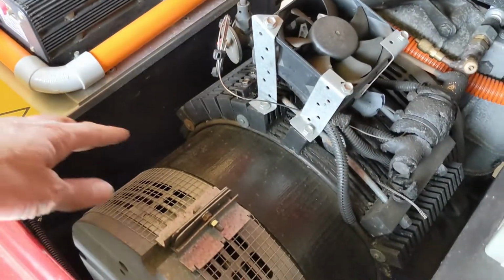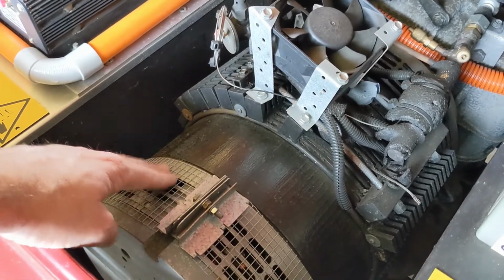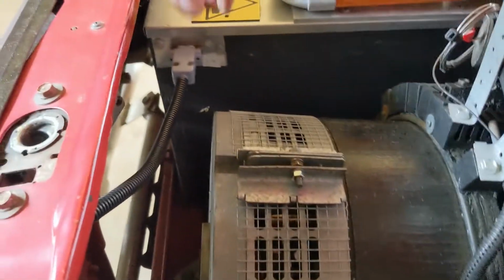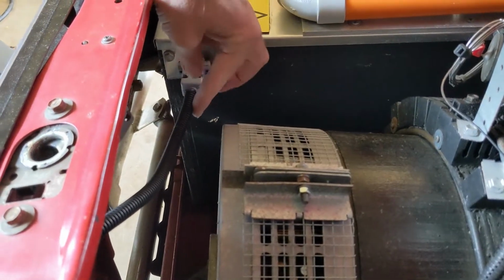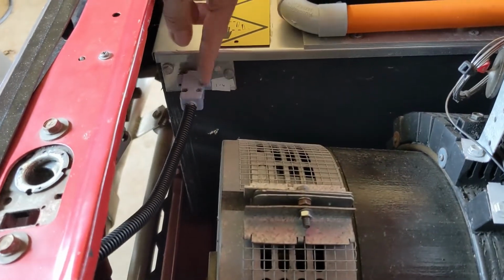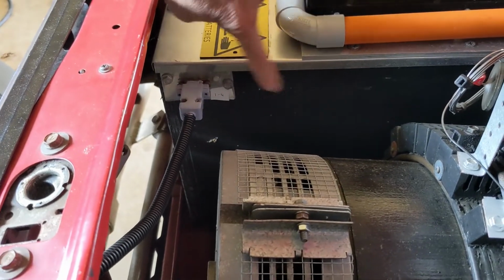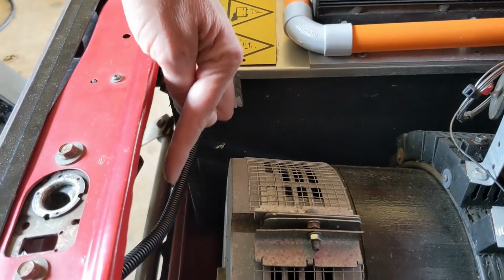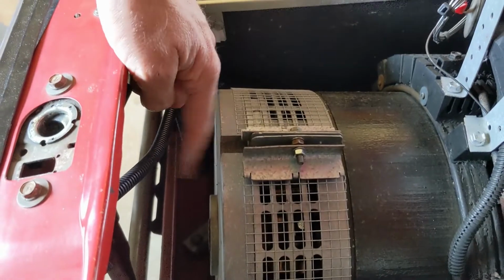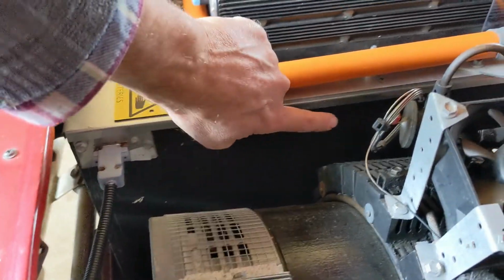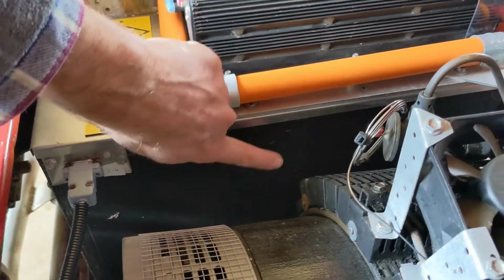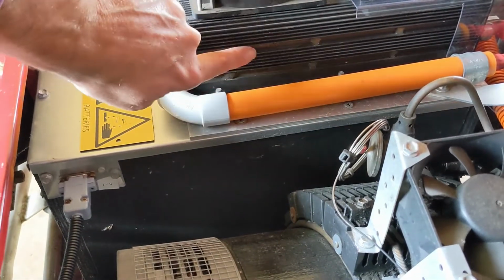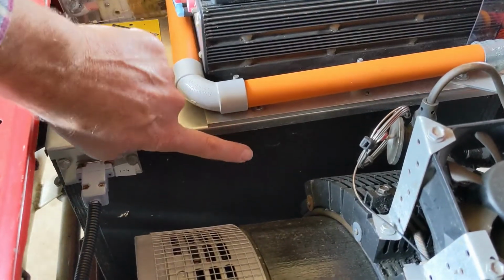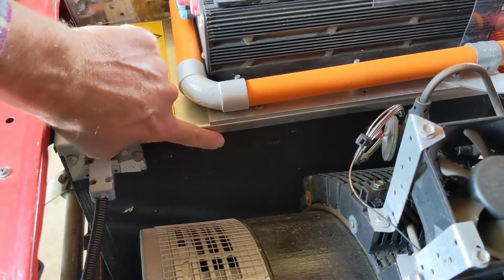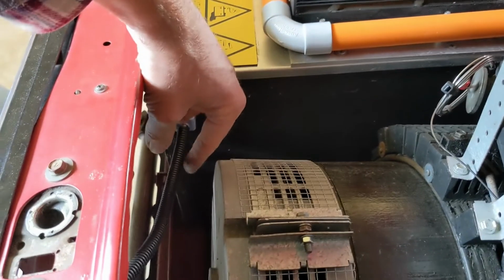The other thing that could be causing the interference is the motor here. So here is the connection for the BMS wires. They go through this here, in through this connector into this box and back out again. It goes in and out through this same one, so it's right in front of the motor. There's also communications up and down inside this box, which is right underneath the controller. It's reasonably difficult to get into that box to provide any further shielding, but it's pretty easy to do this one.